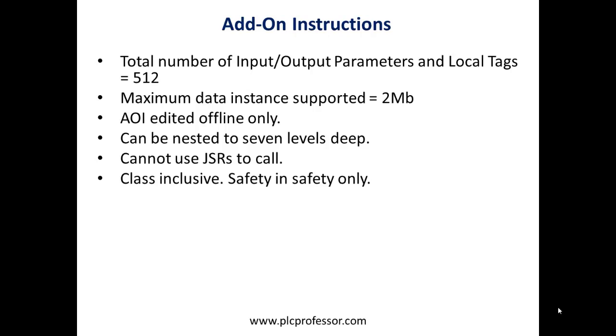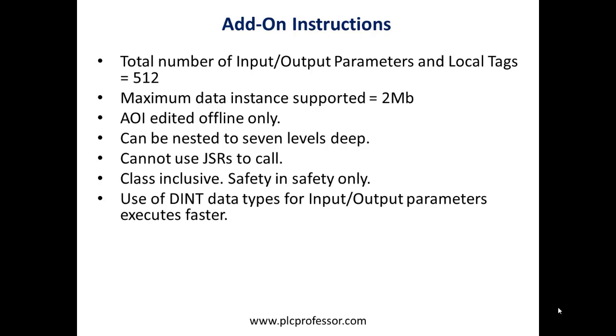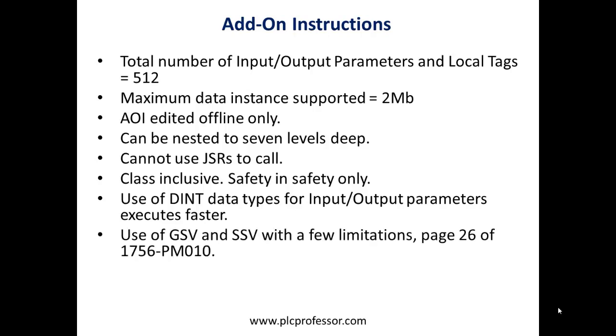Add-on instructions are class inclusive, meaning you can only use safety instructions inside of safety add-on instructions. Use of double integer data types for input/output parameters executes faster. Everything in the Logix engine works faster and better with double integers — 32-bit words. You can use GSV (get system variable) and SSV (set system variable) with some limitations.